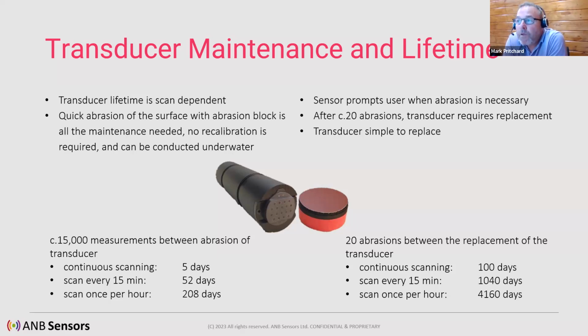Now, it's important to understand that the abrasion can take place in situ, so you don't have to take the sensor out of the fluid or the water that you're measuring. You can go down, you can scrub the sensor in place, and off you go again. It's good to go. If you're doing a measurement every 15 minutes, that equates to 52 days. If you're doing once per hour, that's 208 days. So the intervention required of the sensor is really minimal as we go forward. And the costing of the transducer is very low. But again, please speak with Andrea regarding the pricing of the spare transducers.